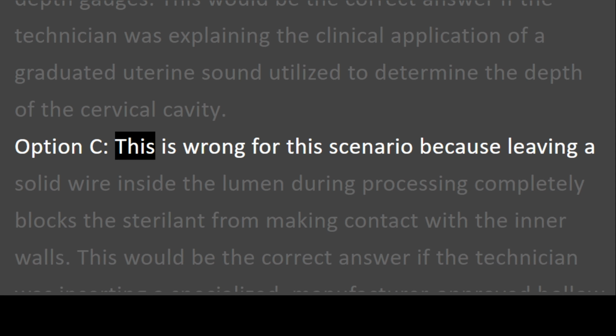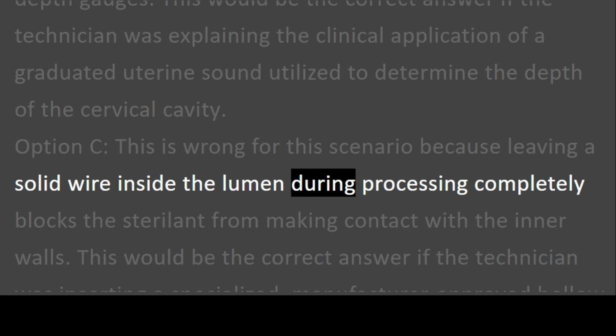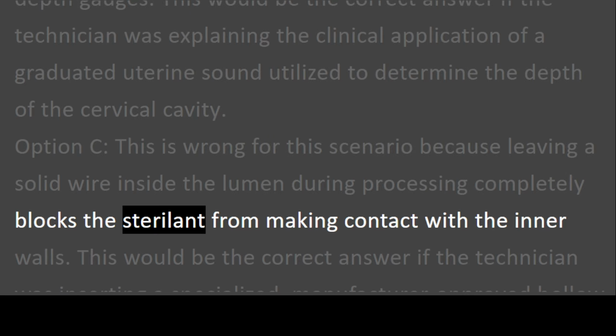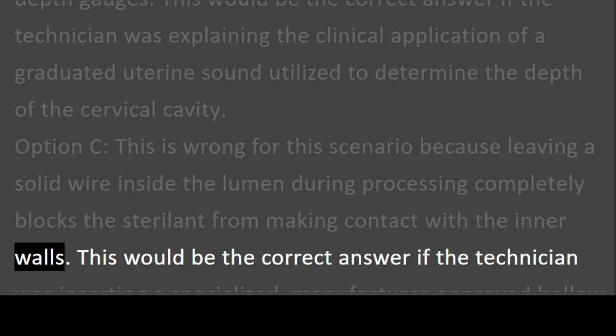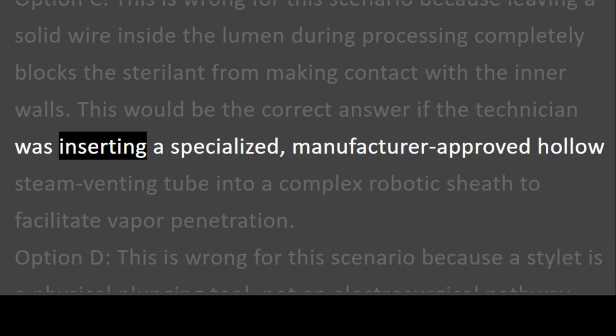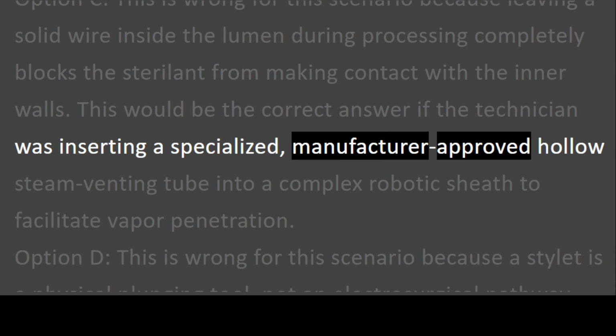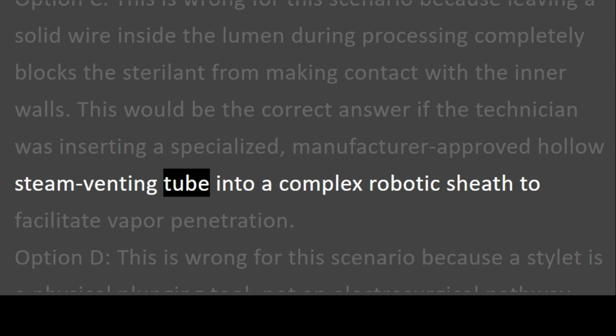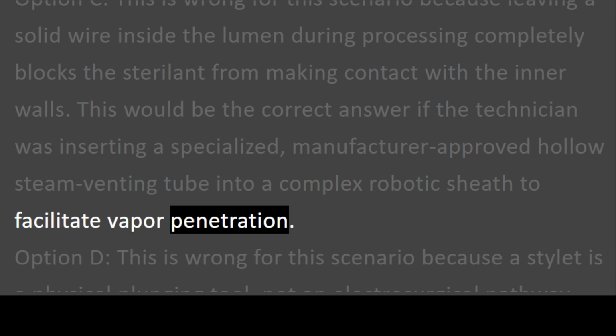Option C. This is wrong for this scenario because leaving a solid wire inside the lumen during processing completely blocks the sterilant from making contact with the inner walls. This would be the correct answer if the technician was inserting a specialized, manufacturer-approved hollow steam venting tube into a complex robotic sheath to facilitate vapor penetration.